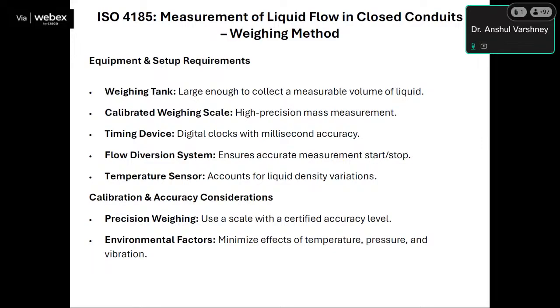Equipment and setup requirements as per ISO 4185: a weighing tank large enough to collect a measurable volume of liquid, and a calibrated weighing scale. A high precision mass measurement system is required. A timing device is required for calculating the time for filling the water tank. And there is a flow diversion system which ensures accurate measurements during start and stop. A temperature sensor is required for measuring the temperature of water at that particular flow rate, which will help you to calculate the density at that particular temperature.